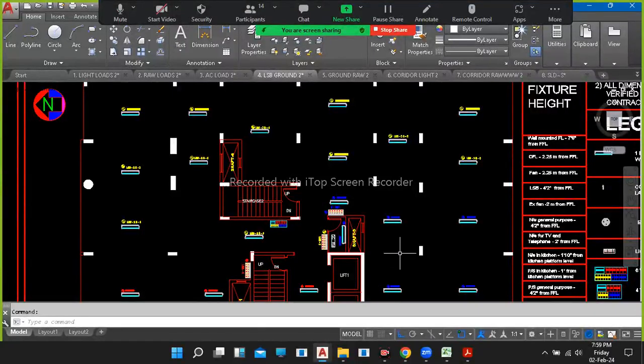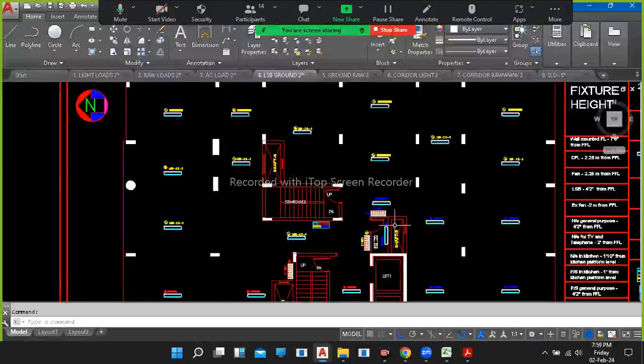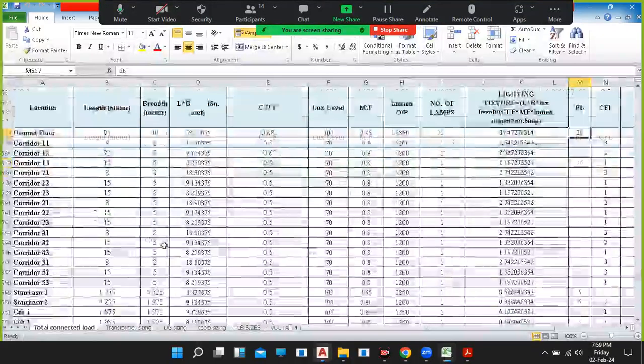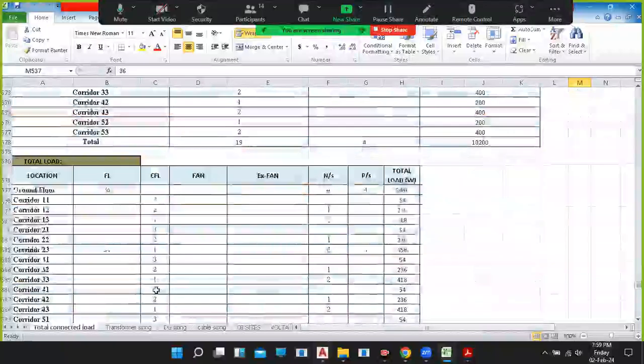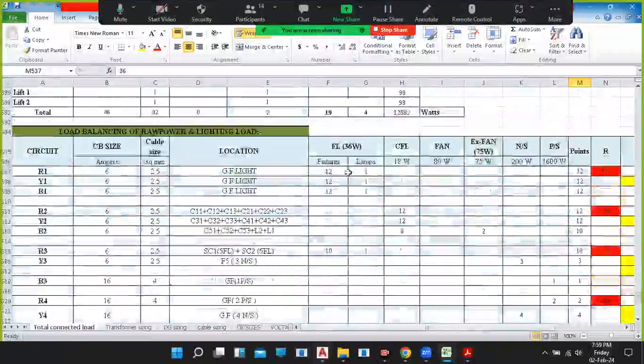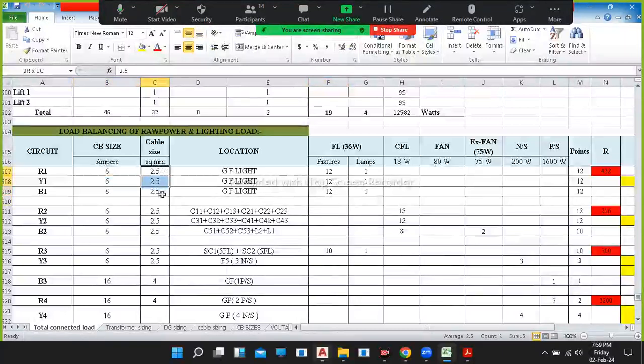No, sir. Because on one phase we can give a maximum of 800 watts and 12 points. So according to that, what he had done is 12, 12, 12 - 3 phases he had taken as per the scheduling sheet. So R1 phase was coming, Y1 phase was also coming, B1 phase also coming - 12 points taken in one phase each. 6A circuit breaker, 2.5 square mm cable, for ground floor lighting.